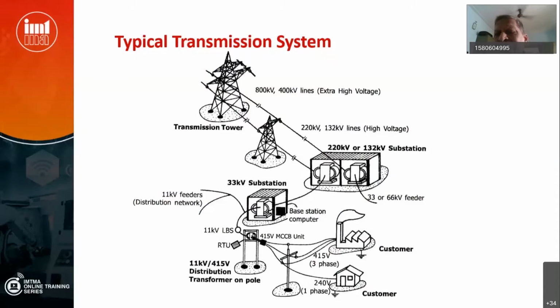Typical transmission system prevailing in the country is like this. If the generating station generates at a particular voltage level, later on to transmit it over a long distance, the voltage is stepped up. That is, the generating station transformers are used. We will be dealing with transformers, also principles of transformers. Here I am only explaining the whole concept of total generation, transmission, distribution, and utilization. First, when it is generated, soon after the generating station nearby, there will be a station with a transformer. It steps up. It can be up to any voltage. Minimum nowadays it is 220, 400 kV. In some cases even 765 kilovolts. It is transmitted at extra high tension, ultra high tension, UHV 765 kV. It is transmitted to different distant places, different load centers.